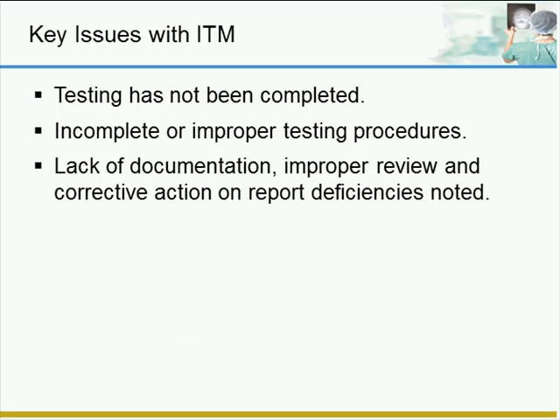Here are some key issues with inspection, testing, and maintenance of sprinkler systems. Some of the things that we find out in the field are that the system has not been properly tested within the time frames, or the testing has been incomplete or improper, or more commonly, that the lack of documentation leads to improper review and corrective action on any deficiencies that may have been noted.